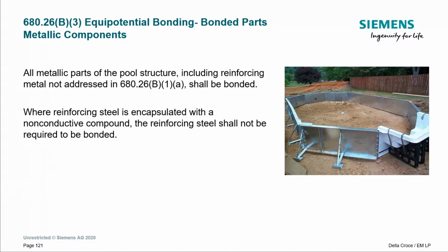You would think so. Now, is there anything introduced into this that is maybe fiberglass that would break up the connection? Let's say there was something on this side that would break this. If I made a bond connection here and this is all bolted together, I'm good. But if there was something on this side that created a separation between this half and this half, then I think I would have to bond each one.